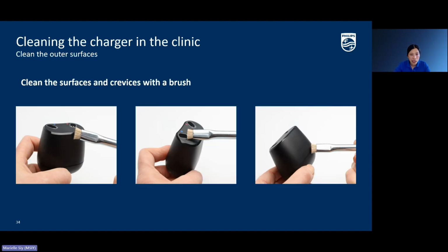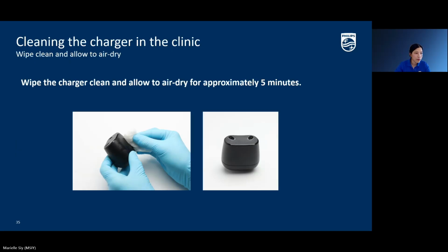Then clean the outer surface. Use a brush to clean the surface and all of the crevices. Then you can wipe the charger clean and allow it to air dry for around 5 minutes. This is the time where you retest. You can place the hearing aids in the charger to check if charging is happening. If it's still not charging, test with your own hearing aids from the clinic. And if the charger still doesn't work with any hearing aids, then that's when you need to have it sent in.